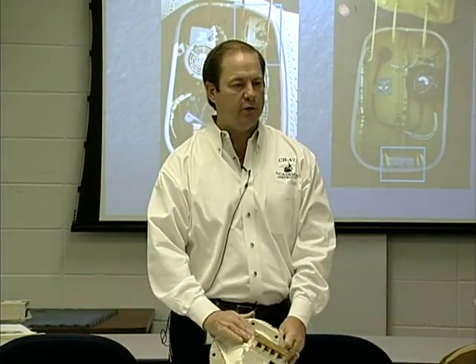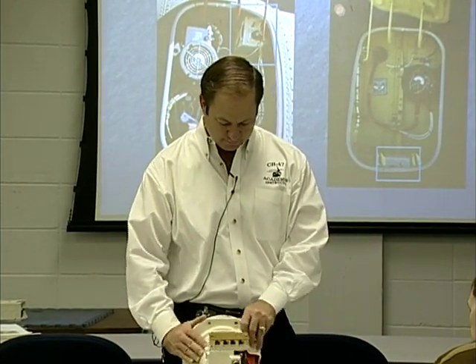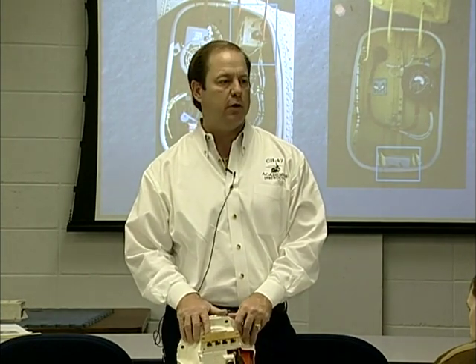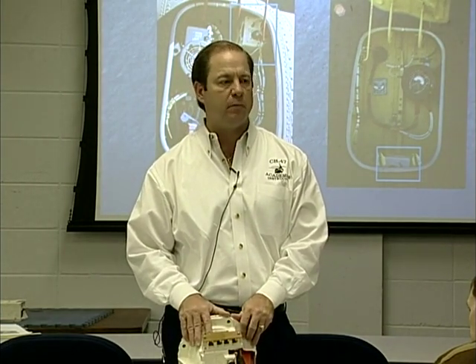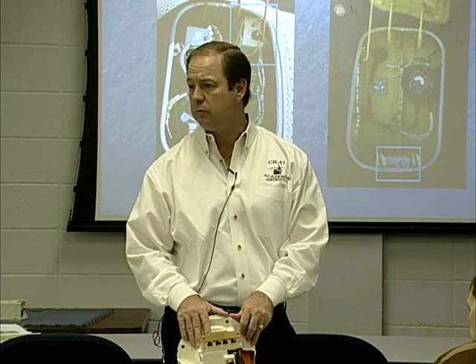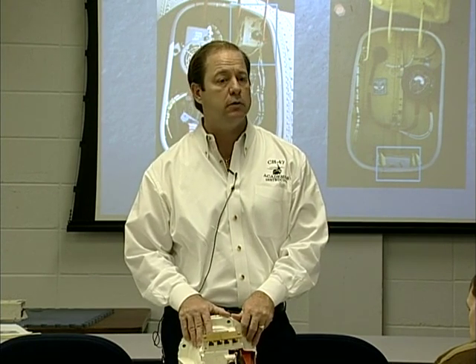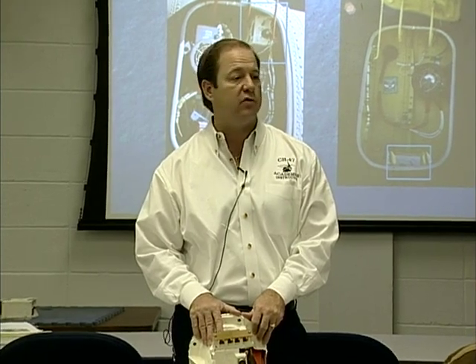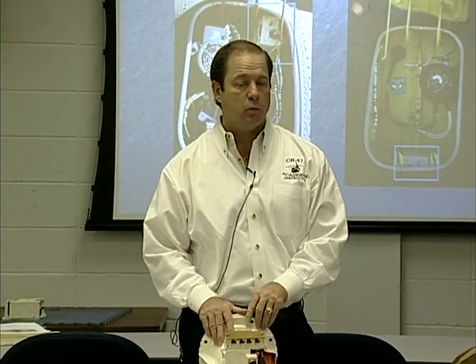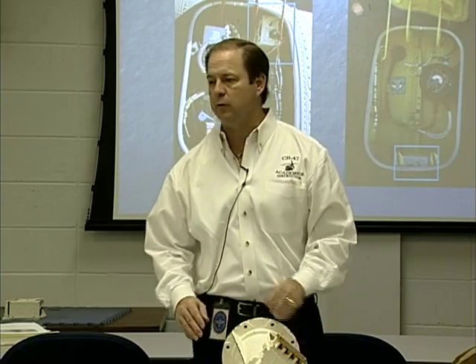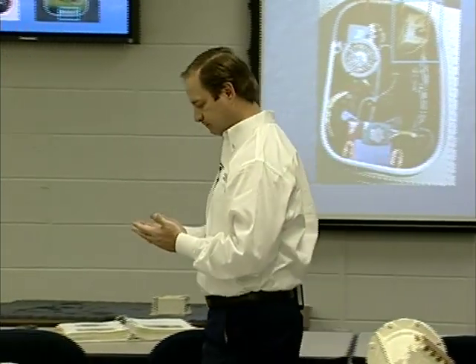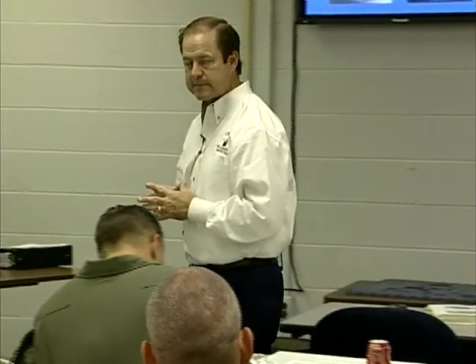The most these generators can provide for, hertz-wise, is 420 hertz - well within the acceptable parameters of all the components and systems. So, over frequency was not a concern, which is why we went to under frequency instead. But what's the problem with under frequency? Why is that a major concern for us?